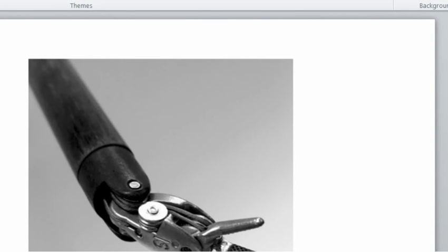To solve the problem due to the lack of force sensing ability, sensing elements must be integrated with the instruments. The size and complexity of such elements depend on the degrees of freedom required for the force measurement. For highly dexterous instruments, especially those of a robotic system, the measurement of force and torque in all 6 degrees of freedom might be most desirable, though not always required. A few degrees of freedom of force measurement would suffice for some specific applications.